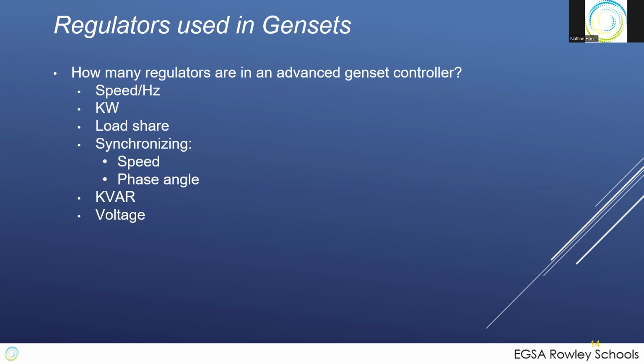But if you tie several gens together in a PPI, a parallel power island, now you have to load share. So you'll have a load share regulator to balance the loads between the generators and regulate that so you don't get into a resonant situation where one kW swings up high, one goes low, and back and forth and back and forth.